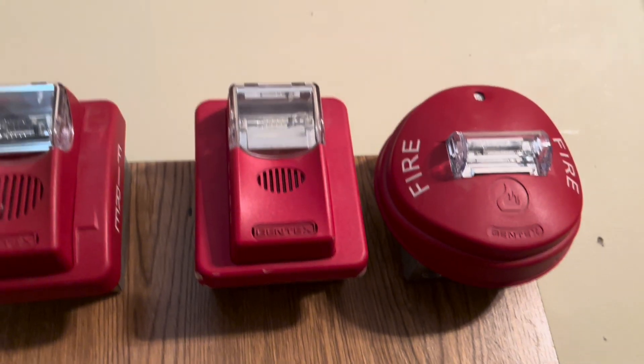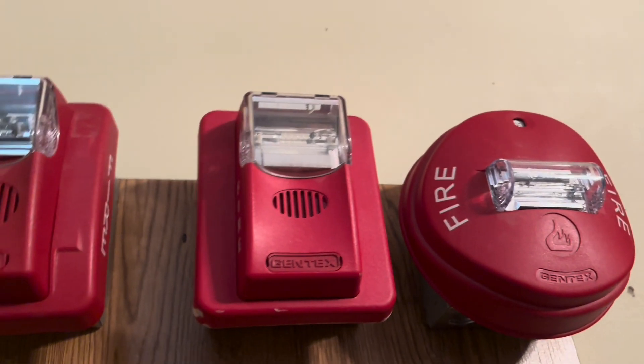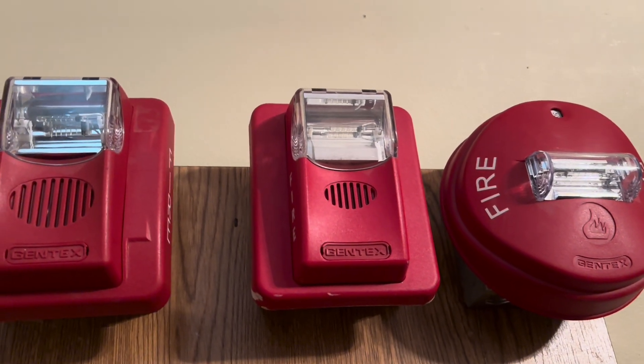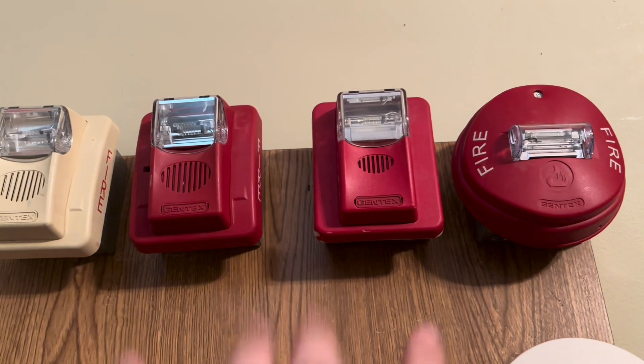Right next to it I have my Gentex Commander 1, fixed 15/75 candela. This is set to continuous but coded to Code 3 by the panel, and four wire as well. All of these will be doing audible silence this test.